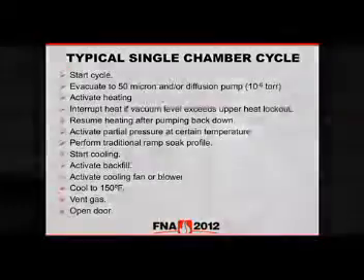If the furnace is equipped with a diffusion pump and your recipe calls for it, a series of valves will close and open, pumping down to maybe 10⁻⁶ range — three more decades below 50 microns. Once down there, the heating system kicks on. As you heat, contamination from wash solution, cutting fluids, grease, or fingerprints causes vacuum levels to shoot up. If heating too quickly, it may shoot over 500-600 microns, shutting down the heat, requiring the whole pump-down sequence to restart. To prevent this, people often ramp up at a slower rate.